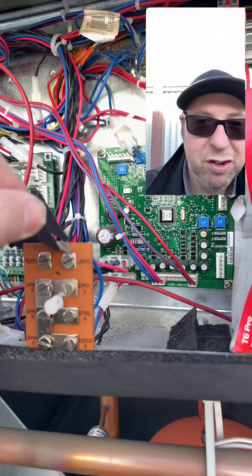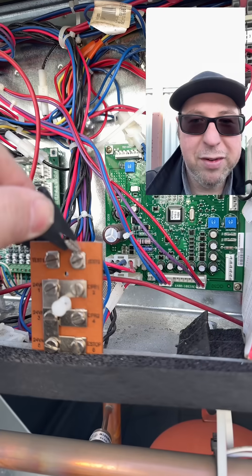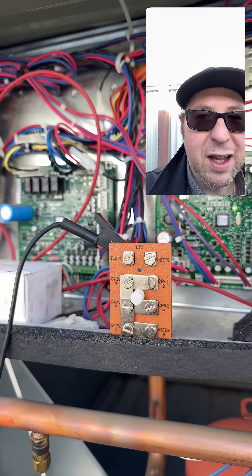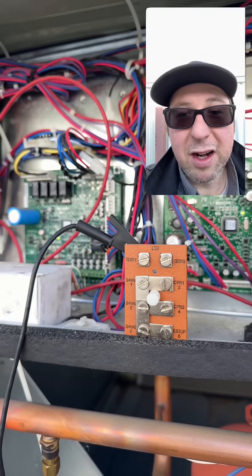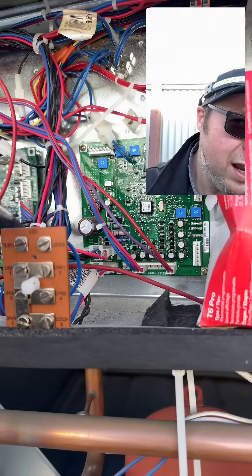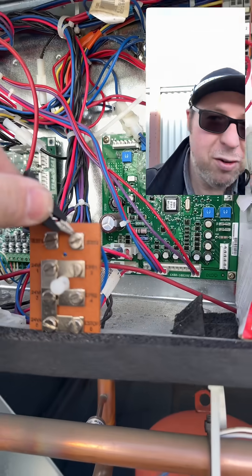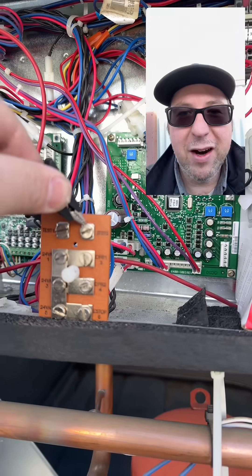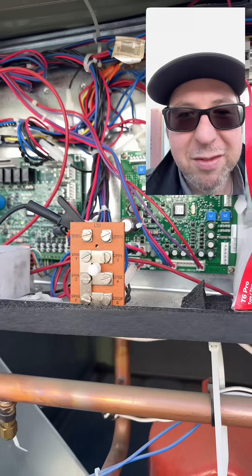Touch it and hold it for about three seconds. That's going to cause the economizer to open. And then if you touch it and hold it for another three seconds, that's going to turn on air conditioning.